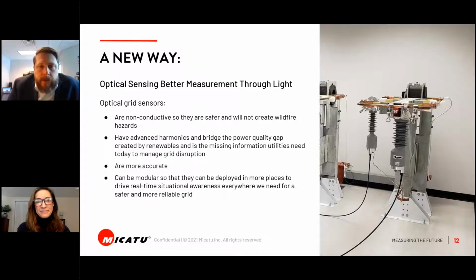The one thing we're fundamentally focused on is changing the way the world senses with light. Optical technology is great for solving some of these problems. There are several differentials between traditional PTs, CTs, resistive technologies and optical technology, because we're a field sensing sensor. What that means is that electrical fields and magnetic fields come out of the power conductors, and we're actually measuring those. So we're not actually moving electrons, and by not moving electrons, there are several benefits.